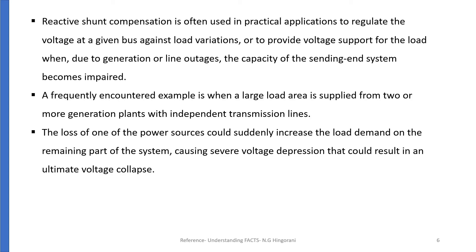Reactive shunt compensation is used in practical applications to regulate the voltage at a given bus against load variations, or to provide voltage support for the load when — due to generation or line outages — the capacity of the sending end system becomes impaired. A frequently encountered example is when a large load area is supplied from two or more generation plants with independent transmission lines.